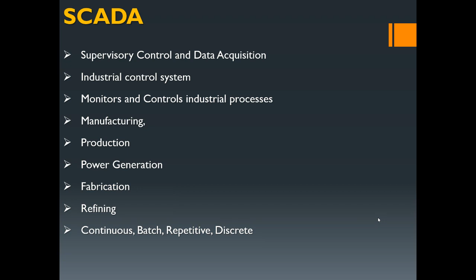Let us talk of the components of SCADA system. It has the human machine interface, HMI. This is the operator window of the supervisory control system. It presents in front of the operator the plant information in graphical form, which forms mimic diagrams, which are the schematic representations of the plant being controlled. The HMI is linked to the supervisory computer to provide the live, real-time data to drive the mimic diagrams, alarm displays, and the trending graphs. Most installations of the human machine interface are a graphical user interface for the operator, which collects the data from the external devices, creates reports, performs alarming, and sends notifications.